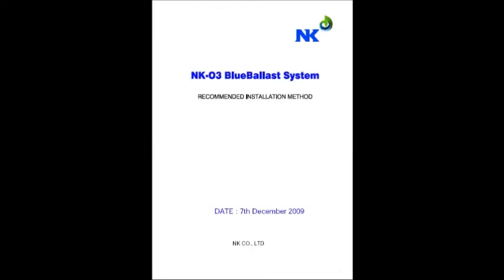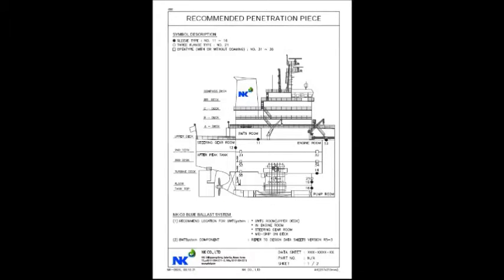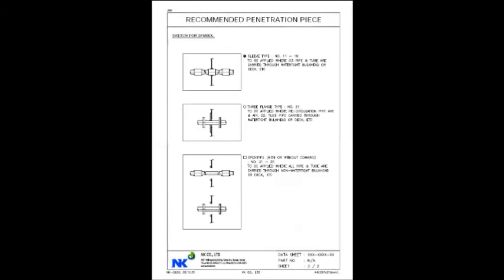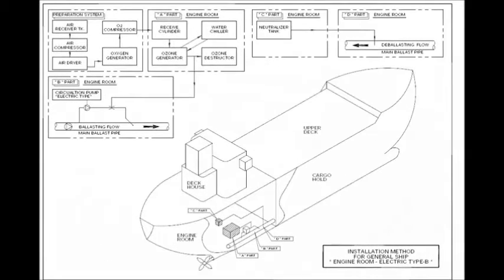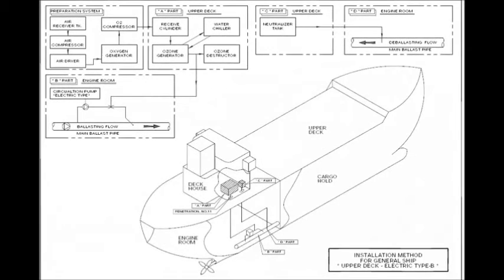The installation of NK03 blue ballast system is so flexible according to the ballast pump location on board. In the tank vessel, if ballast pump is located in pump room, only ejector and nozzle injecting ozone is required to be fitted at ballast pump discharge side and others can be located in engine room or accommodation or on deck as available space. Also, no explosion proof electric materials are requested.